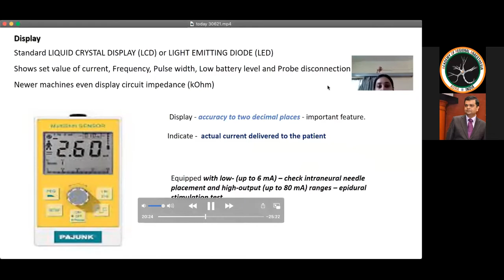There should be a clear digital display of accuracy to 2 decimal places, which is one of the important features of the nerve stimulator, and it should also display the actual current delivered to the patient and not simply the set value of the current settings. It should also be equipped with low and high output ranges, as the low output ranges are used to alert the operator if there is any potential nerve damage or intravascular placement, and the high ranges from 1 to 10 milliampere are used for the epidural stimulation test.